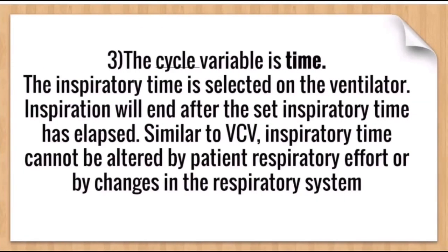Now the third thing is the cycle variable. The cycle variable here is time. So the time will determine when the inspiration has to end. So the inspiratory time is selected on the ventilator. The inspiration will end after the set inspiratory time has elapsed.